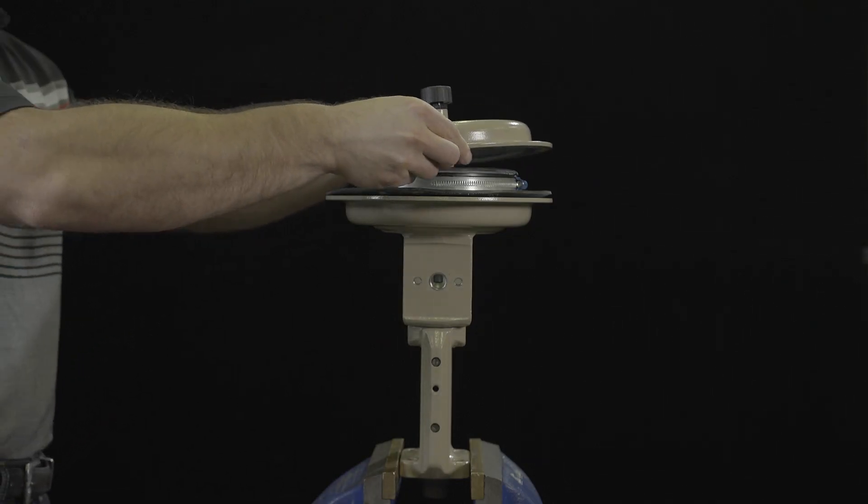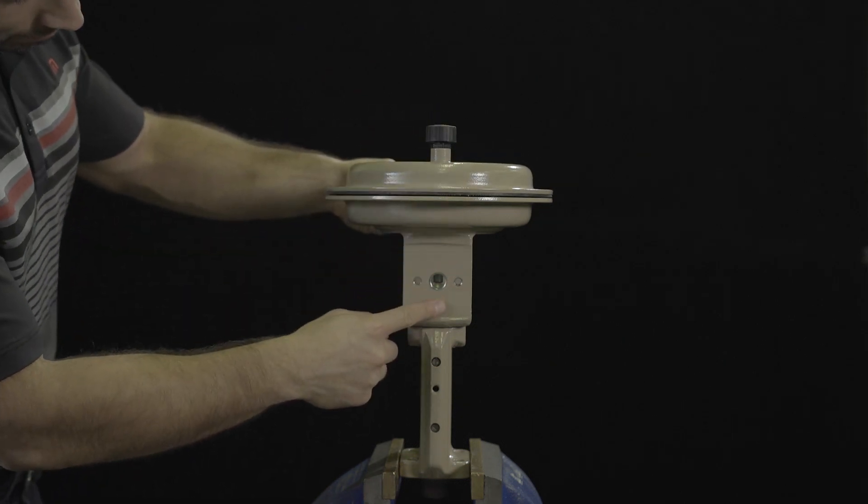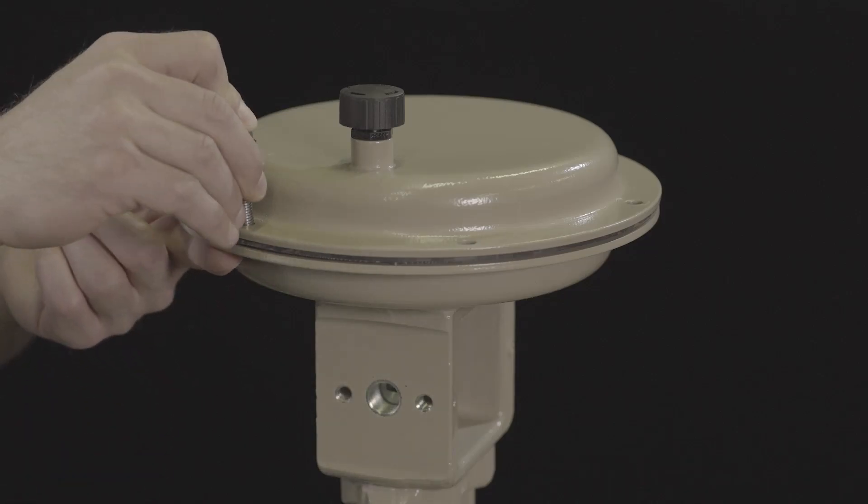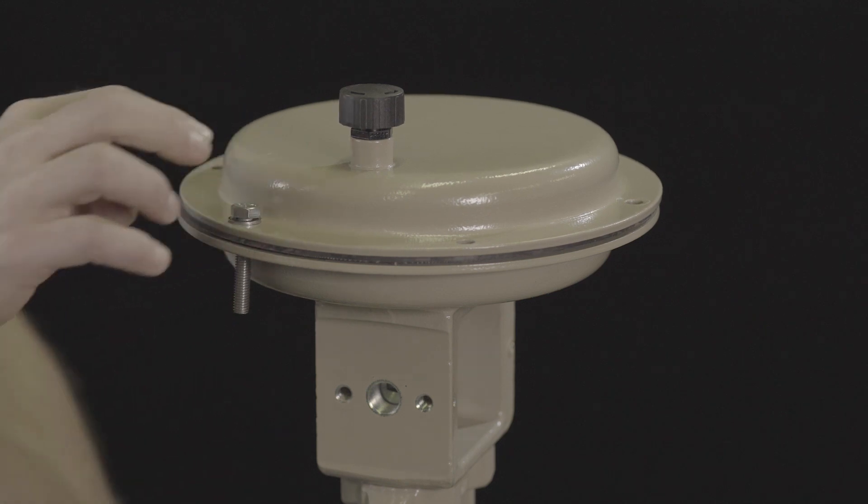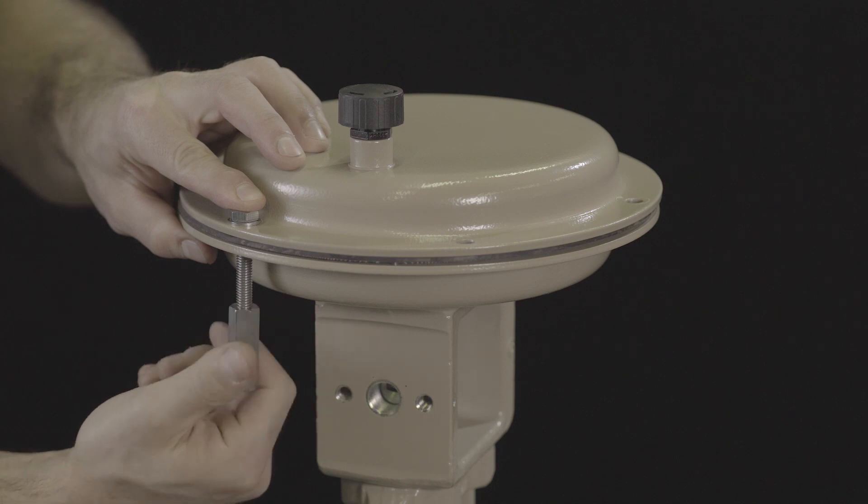Place the top of the actuator case onto the assembly. Ensure that the air connections on the cases are correctly aligned with each other. Fasten the top and bottom diaphragm cases together using the nuts and bolts. Observe tightening torques.